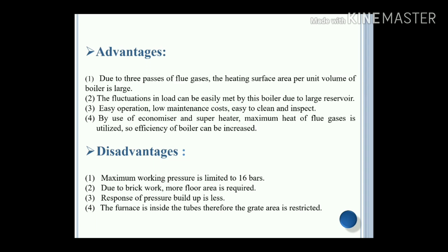Some disadvantages of the Lancashire boiler: maximum working pressure is limited to 16 bar only. Due to the brickwork, more floor area is required. Response of pressure build-up is slow. The furnace is inside the tubes, therefore the grate area is restricted.